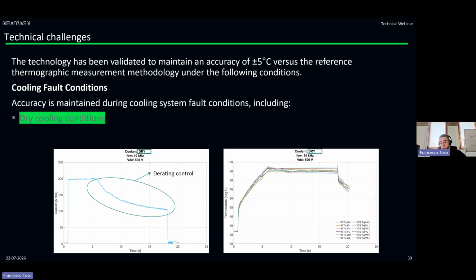So in this case, the fault is no longer in the pump, but in the pipe. So basically, you have some leak, and inside the inverter, you don't have any more water glycol. So let's say that the inverter is completely healthy. It's not broken. It's not on fault. It's the cooling system that is on fault. Now, if you don't have coolant inside the cooler, the dynamic is quite fast, because you have air. You no longer have the water mass capacity, and the classical functional safety procedures are not fast enough to recover and improve the safety of the inverter during cooling system faults in this case.